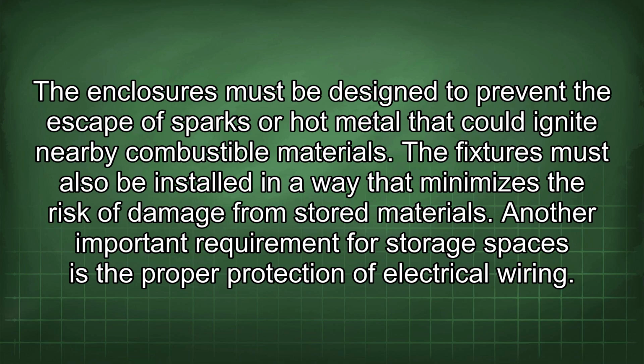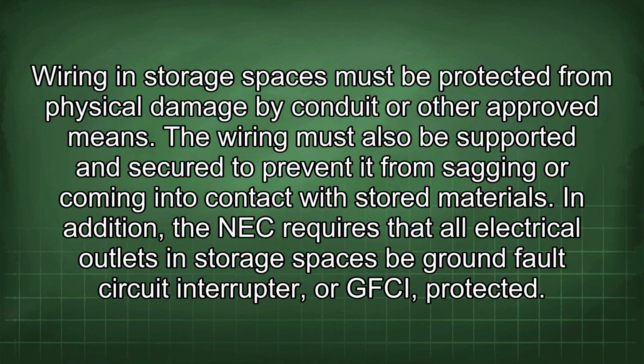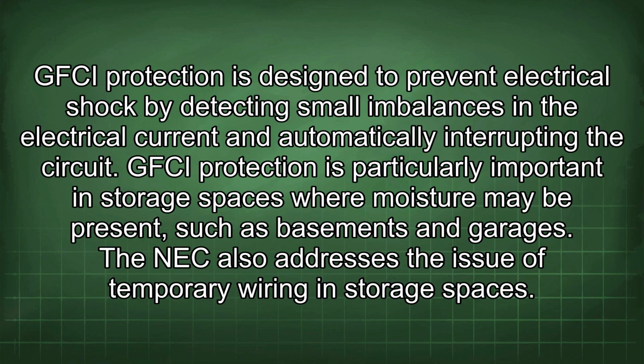Another important requirement for storage spaces is the proper protection of electrical wiring. Wiring in storage spaces must be protected from physical damage by conduit or other approved means. The wiring must also be supported and secured to prevent it from sagging or coming into contact with stored materials. In addition, the NEC requires that all electrical outlets in storage spaces be ground fault circuit interrupter, or GFCI, protected. GFCI protection is designed to prevent electrical shock by detecting small imbalances in the electrical current and automatically interrupting the circuit. GFCI protection is particularly important in storage spaces where moisture may be present, such as basements and garages.